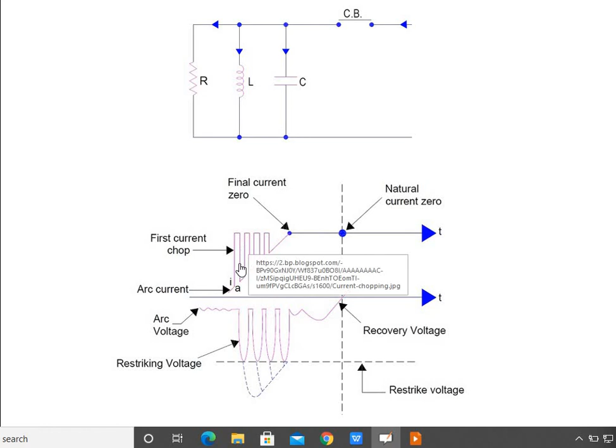So again current chopping will be there, a second current chopping, but in the second case the magnitude of this current will be less, so the prospective voltage produced will also be less. So a number of current choppings are required to avoid the restriking of the arc in the circuit breaker. For that we have taken one example also. We have seen that the magnitude of the prospective voltage is very large, and from this figure we can easily understand. This happens because of the dampening effect of the losses in the equipment, like eddy current losses and hysteresis losses.